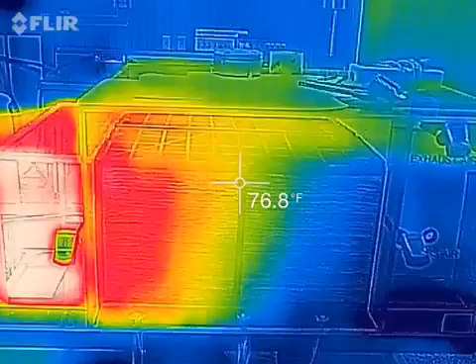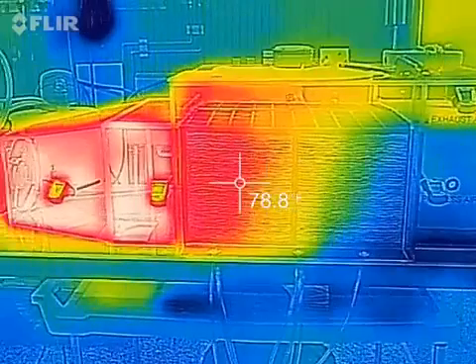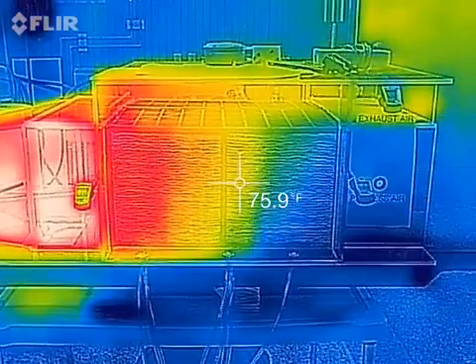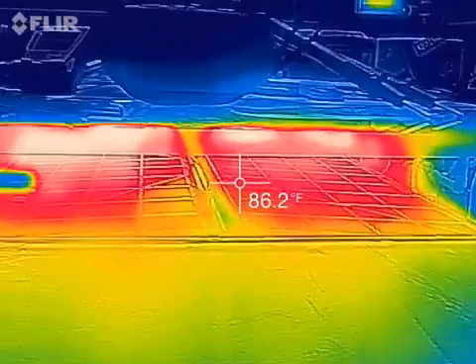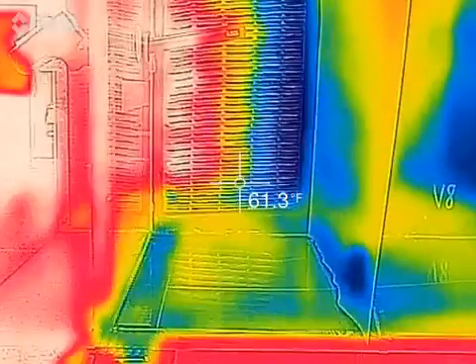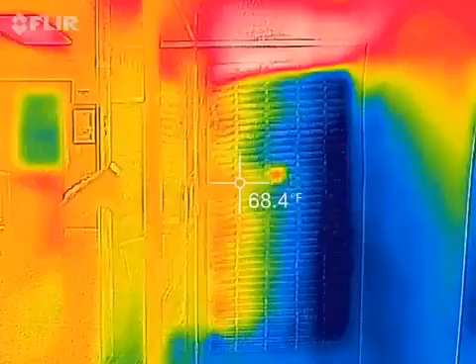You can see the hot, dry air comes in the HMX — this is the side exhaust port — so humidification is happening perpendicular to the process air, which comes out the top. The exhaust humid air is in the 80s at a relatively high humidity of 97%. The cooled process air is coming out at an average of 68 degrees Fahrenheit.